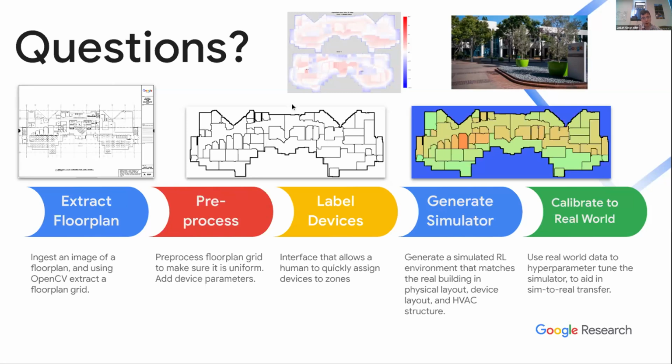So once we have our floor plan with the locations of devices for our new building, we would then really need to do the tuning from scratch, which I think may have been your question. The hyperparameter tuning that we did on our building, we don't expect that to translate to a new building. The thought process is we may want to do independent training for every single building. So ideally, we would have maybe 2-3 weeks of data on this new building, and then we would use that to hyperparameter tune from scratch for this new building.